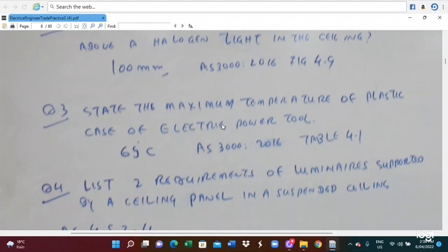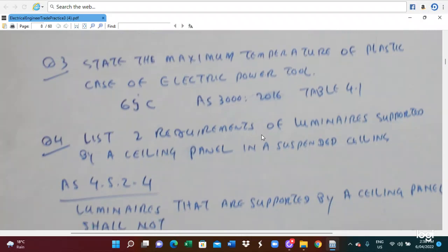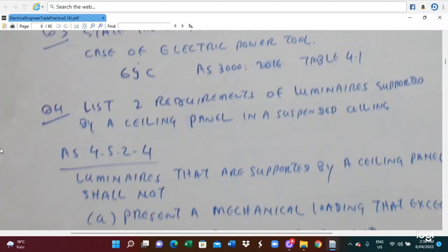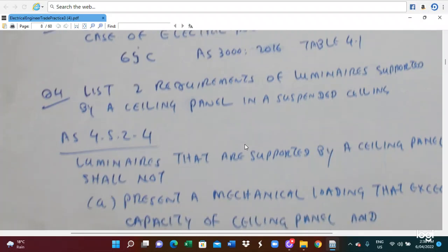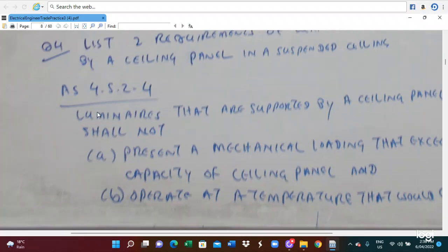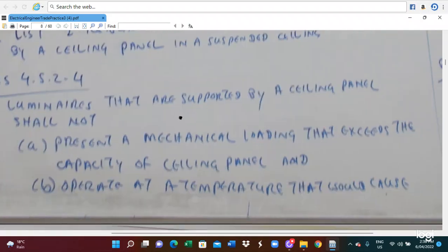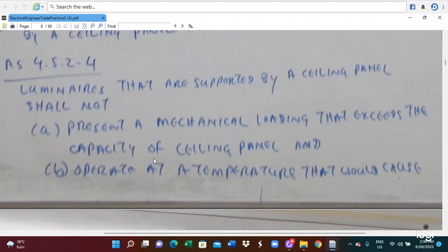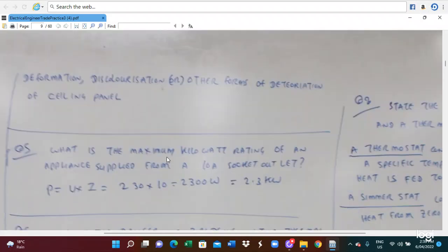What is the maximum temperature of the plastic case of the electric power tool? It is 65 degrees centigrade. You have to refer to AS3000, table 4.1. And list the two requirements of a luminaire put on the ceiling panel in a suspended ceiling. In this case, we refer to AS3000 clause 4.5.2.4. The luminaire put on the ceiling panel shall not present a mechanical loading that exceeds the capacity of the ceiling panel, and shall operate at a temperature that will not cause damage.